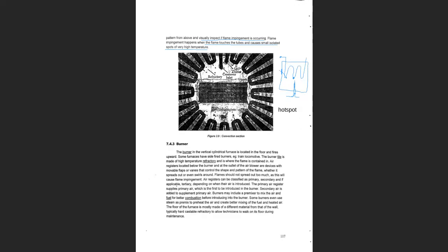فنفس المسألة هنا موجودة، لكن we don't want the flame to touch the tubes because otherwise you will have localized hot spots. وهذه الهوت سبوت مثل ما ذكرت لو ما حد انتبه لها زين ممكن لا قدر الله ينكسر التيوب ويبدأ يصير عندك you will have a huge fire inside the firebox.